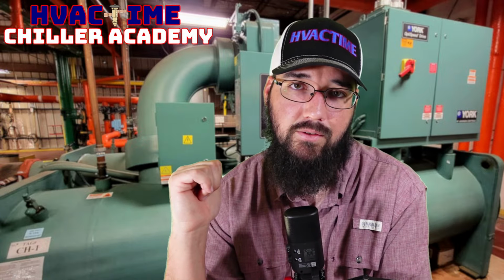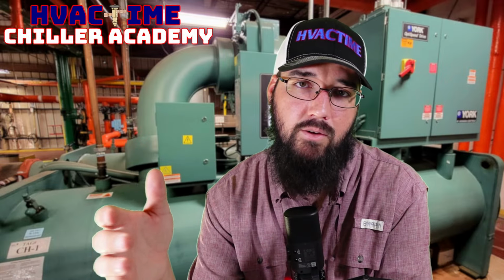Because basically, okay, what are we doing with that chilled water? We've taken that chilled water and we're putting it through, typically in a comfort cooling scenario, we're not talking about industrial, an air handler that is then having air move over that coil and putting heat into the water, and the water carries the heat back to the chiller. Whereas with a DX system, we're just having the air pass directly over that refrigerant.